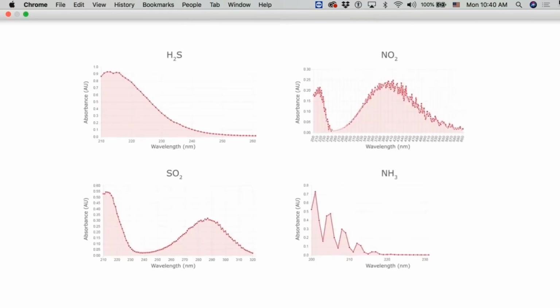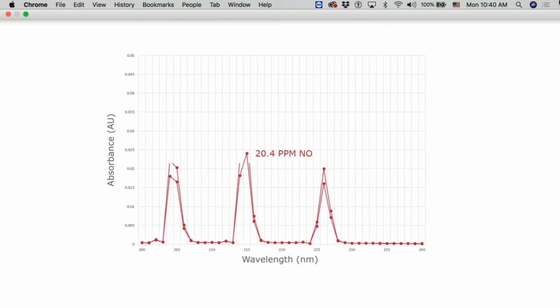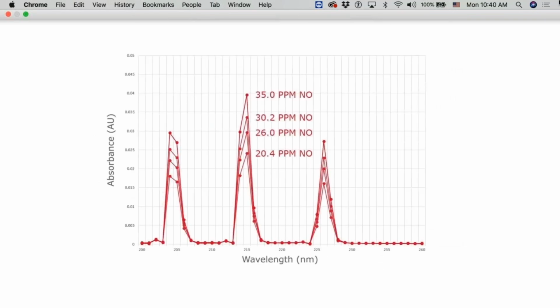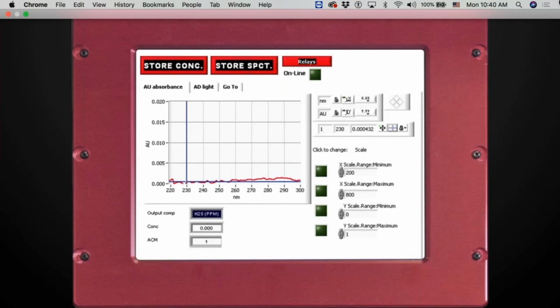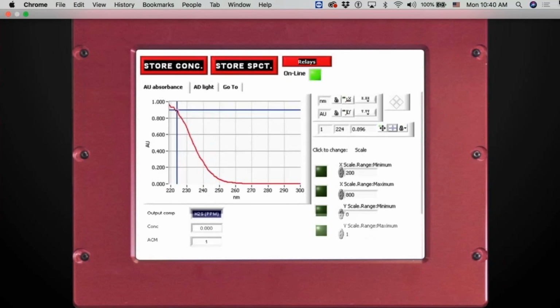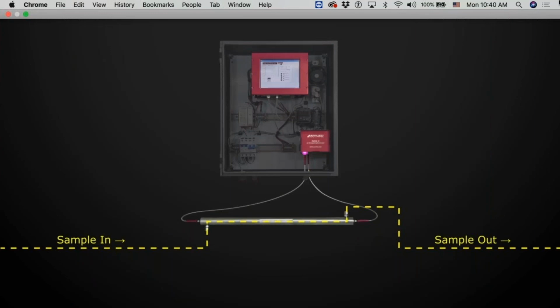interactions. Because absorbance spectra are uniquely characteristic to each desired component and are directly proportional to the component's concentration, the OMA 300 can output these concentrations of the process sample fluid in real time. From xenon lamp to diode array, the entire cycle occupies a few milliseconds and involves no moving parts.